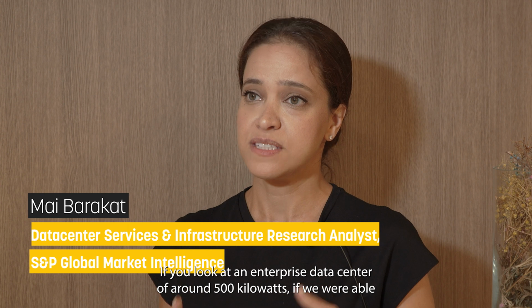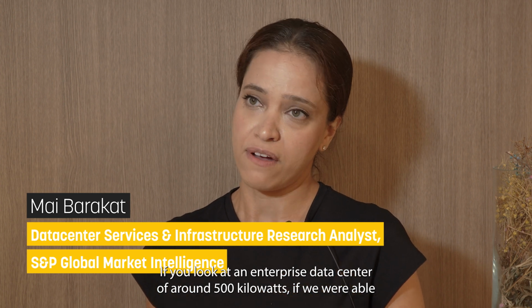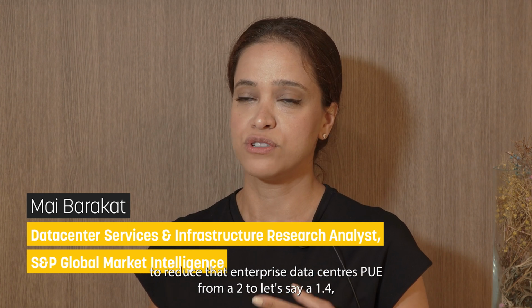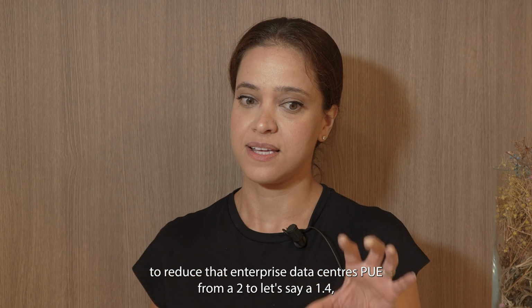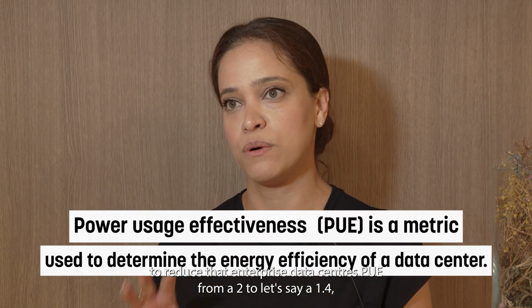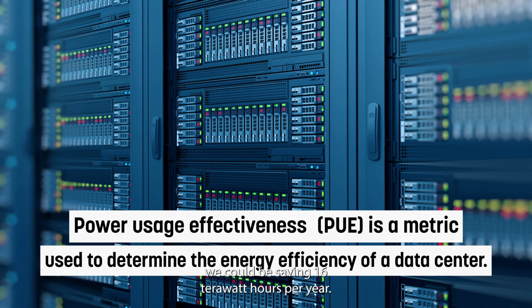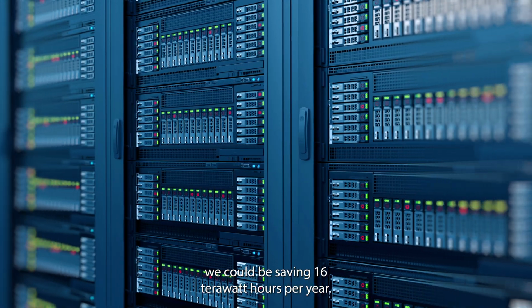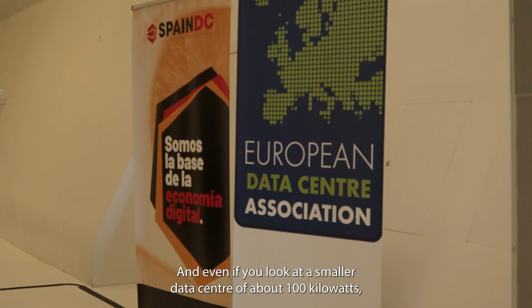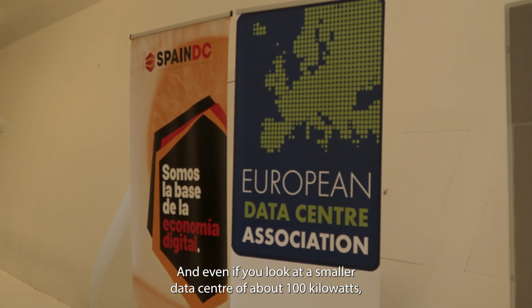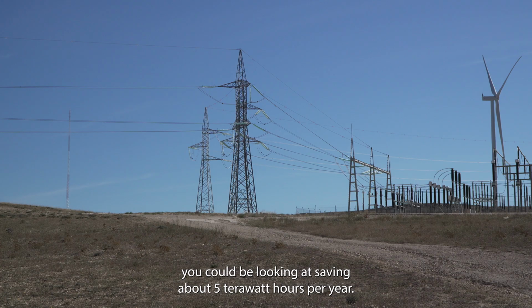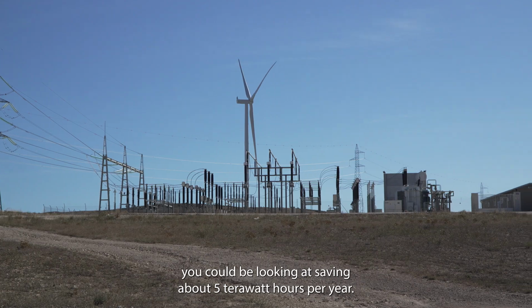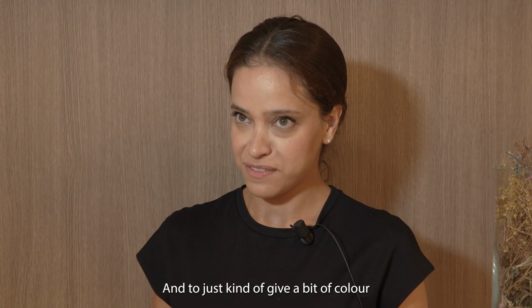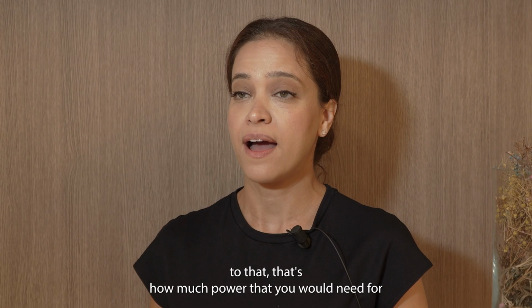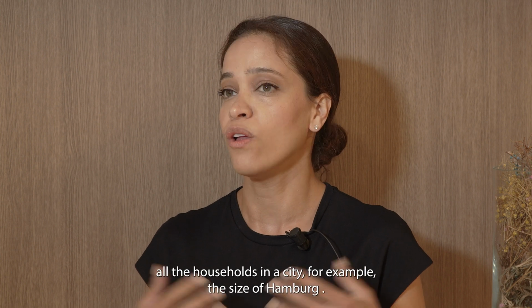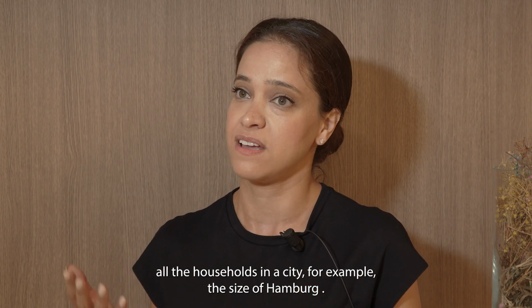If you look at an enterprise data center of around 500 kilowatts, if we were able to reduce that data center's PUE from a 2 to, let's say, a 1.4, we could be saving 16 terawatt hours per year. Even a smaller data center of about 100 kilowatts could save about 5 terawatt hours per year. To give some color to that, that's how much power you'd need for all the households in a city the size of Hamburg.